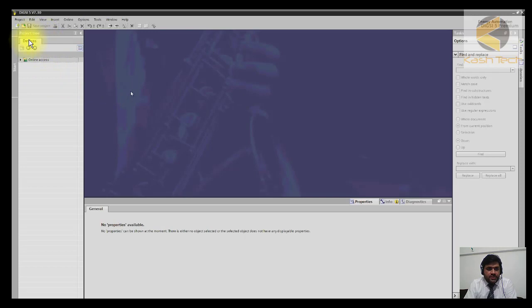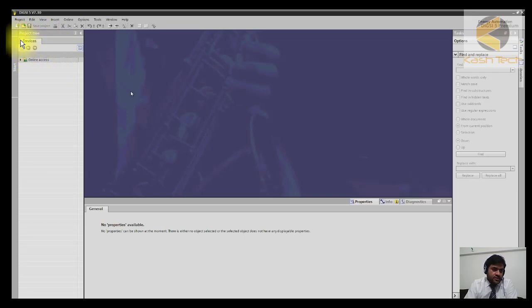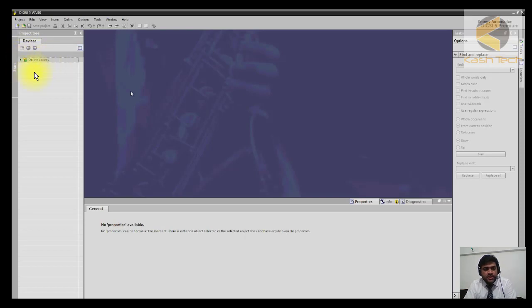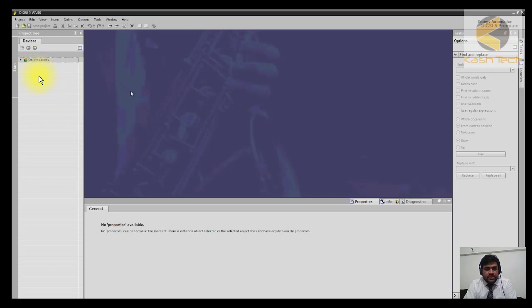Once you open the DIGSI file, on the left side you will see the project tree. In the project tree, at the bottom you will see Devices and Online Access. For example, you can add a new project here. If you have a 132 kV substation, you can add a new project — 132 substation — and then have different voltage levels like 132 kV, 33 kV, and other kV levels.